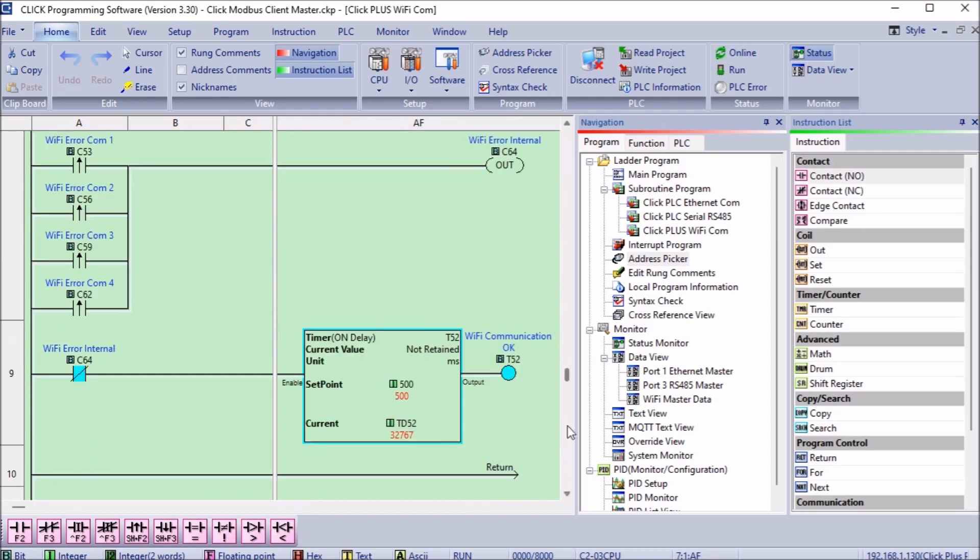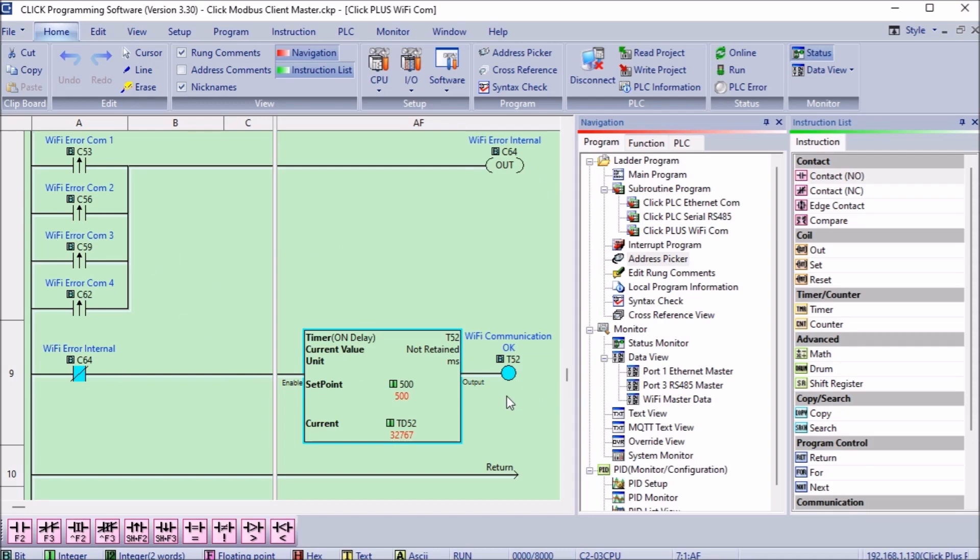The click client PLC will also need to know if the information is valid. We are looking at the leading edge of each of the Ethernet error communication bits. This will trigger an internal bit. The normally closed of this bit will turn on a timer. The timer is set for 500 milliseconds. If the timer done bit is on, then communications are okay. We can use this in other areas of the program.